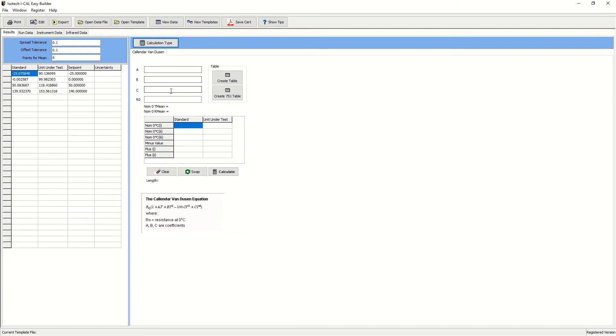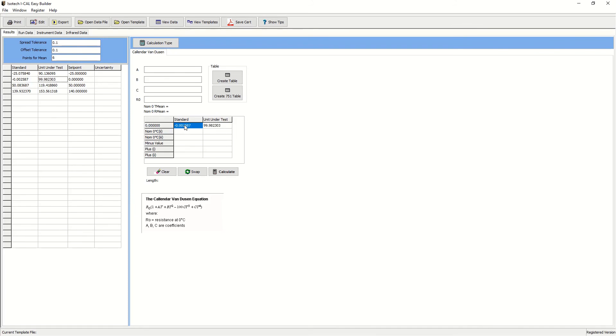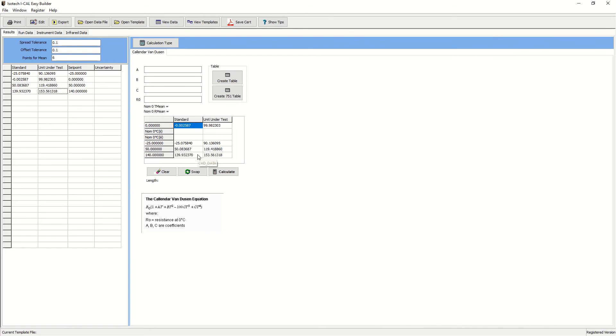So for instance, if we chose Callendar-Van Dusen, we would just, as earlier, simply drag and drop the results into the appropriate boxes and calculate. So by way of example, we'll drag and drop the value at zero degrees C. We'll then take one negative value and two positive values, press calculate and here are our Callendar-Van Dusen coefficients.